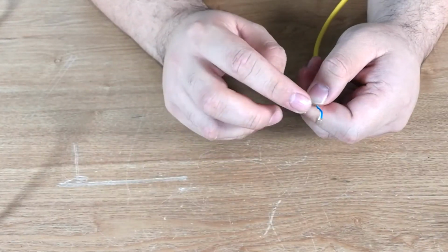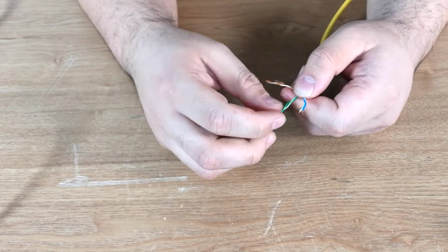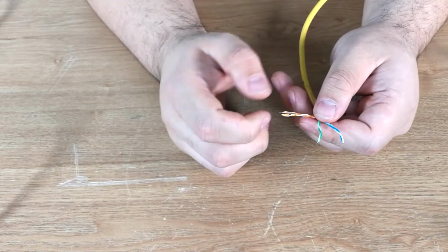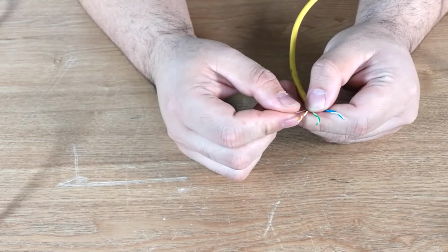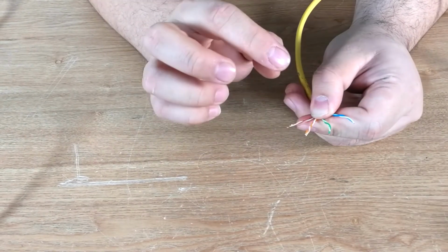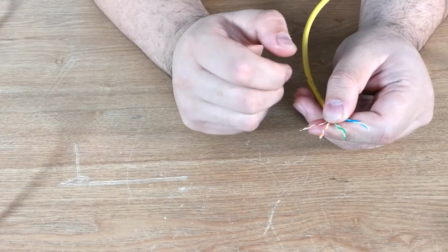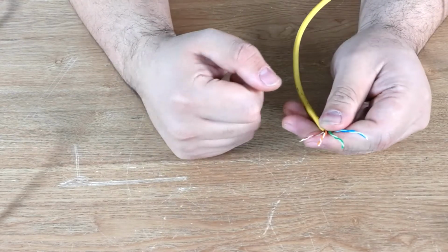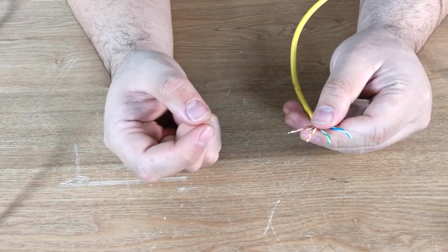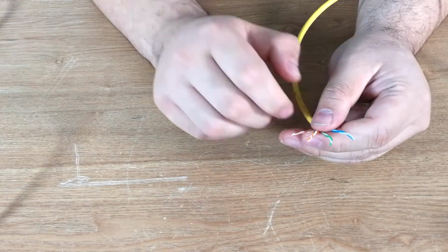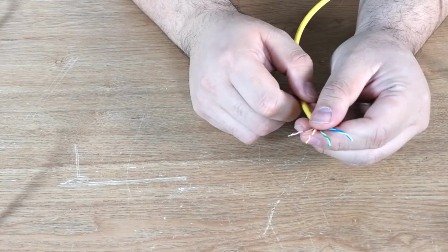If it is a newer model of power supply equipment, it will transmit the power and data on these 2 pairs. But when it comes to older devices, the technology was not mature then, and they would choose these 2 vacant wires and transmit the power through here. In the previous video, we used a splitter to physically divide the power and data from an Ethernet cable and then power 2 IP cameras.